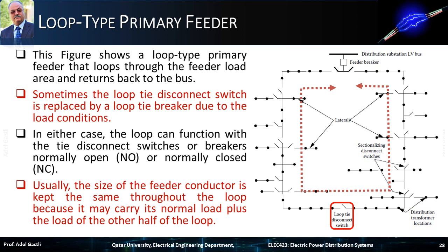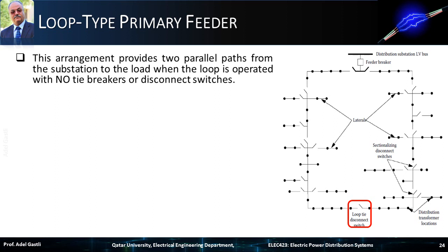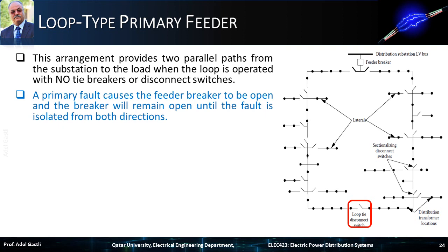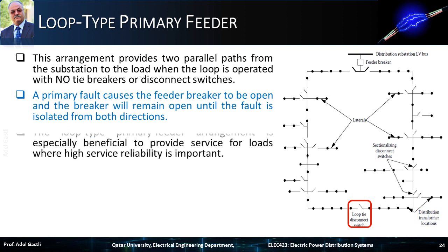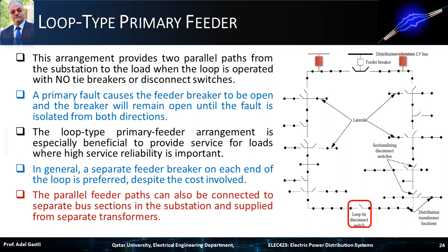Usually the size of the feeder conductor is kept the same throughout the loop, because it may carry its normal load plus the load of the other half of the loop. This arrangement provides two parallel paths from the substation to the load when the loop is operated with normally open (NO) tie breakers or disconnect switches. A primary fault causes the feeder breaker to open, and the breaker will remain open until the fault is isolated from both directions. The loop type primary feeder arrangement is especially beneficial to provide service for loads where high service reliability is important. In general, a separate feeder breaker on each end of the loop is preferred, despite the cost involved. The parallel feeder paths can also be connected to separate bus sections in the substation and supplied from separate transformers.